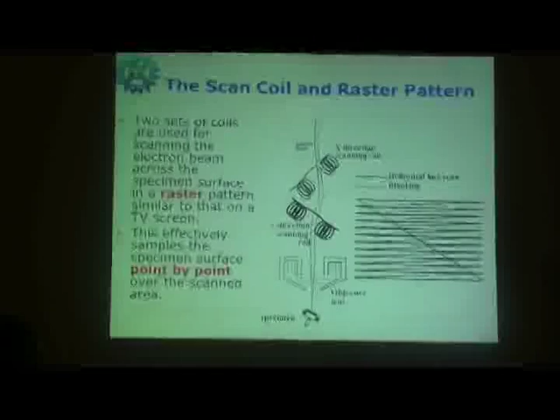Why do we call it a scanning electron microscope? Here the beam is scanned over the specimen that you are seeing. It starts and scans like this, coming back like this, which is called progressive scanning. You have different scannings, you know that. This is a progressive scanning starting from here that scans this sample. It means you have a scan coil which controls the beam to scan over the sample. This scan of a particular area we can do by exciting the scan coils somewhere here.